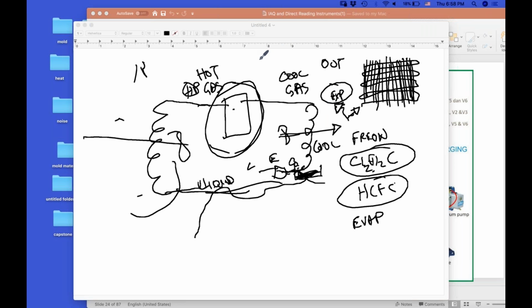If I were to say to myself, it's too much trouble to move this backwards, if I were just to valve this so that I can connect a switch to the couple of valves in here, and that switch would say summer and winter, that's a heat pump. Down in Florida they have them all over the place. You just turn it from heat to cool. All it's doing is switching the coils. So you're heating with the same air conditioning unit that you're cooling with.